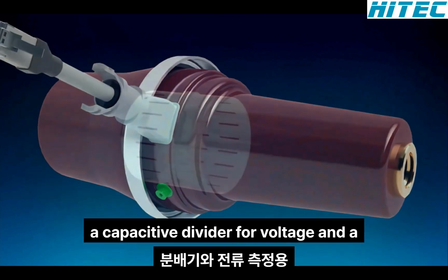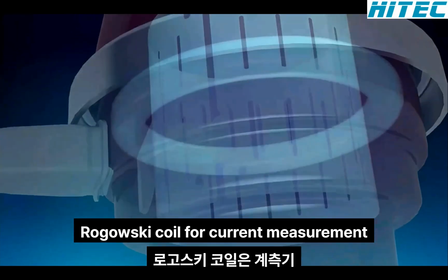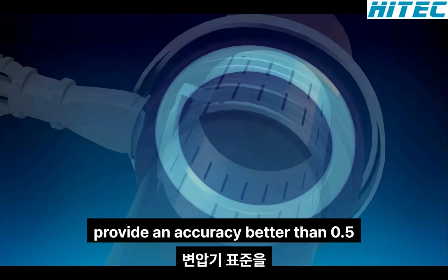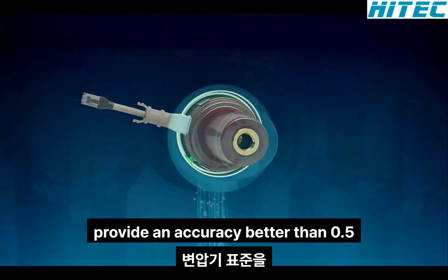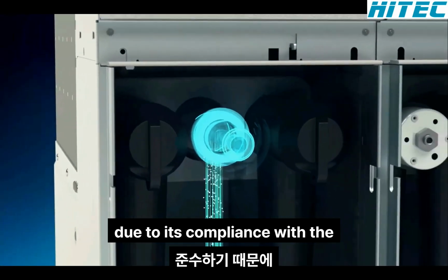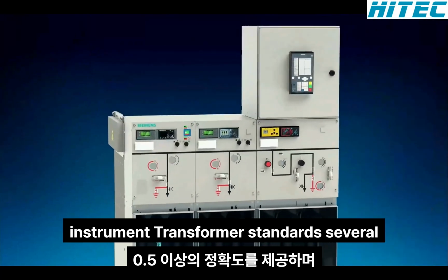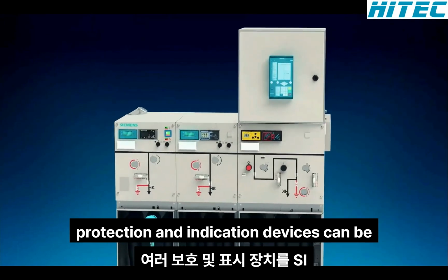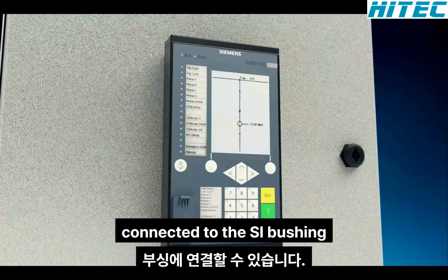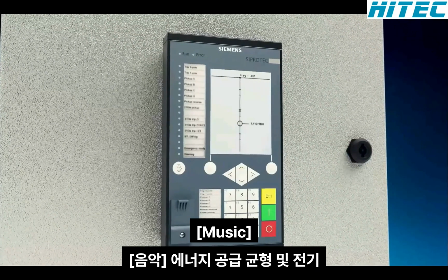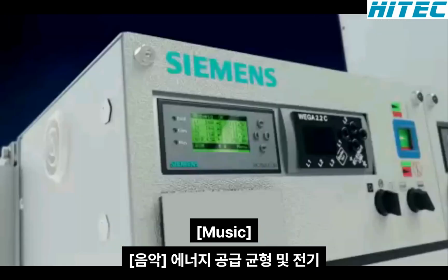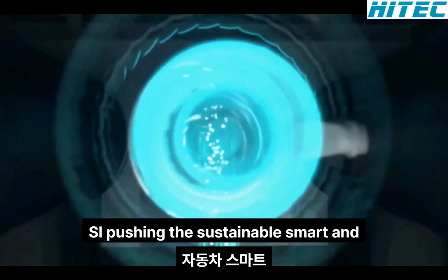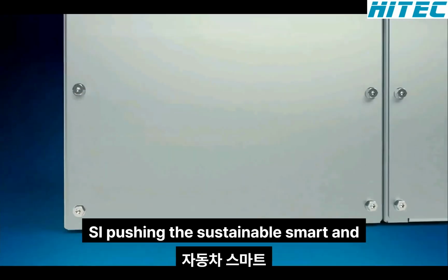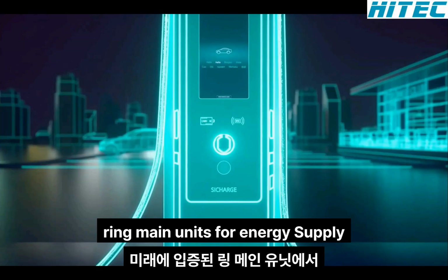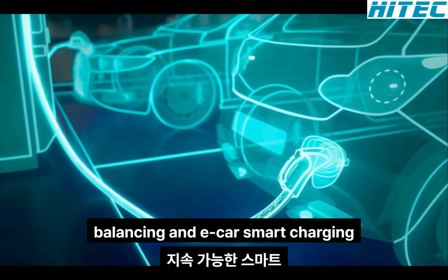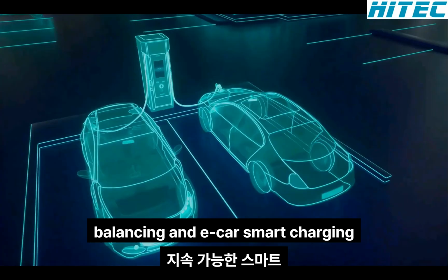A capacitive divider for voltage and a Rogowski coil for current measurement provide an accuracy better than 0.5. Due to its compliance with the instrument transformer standards, several protection and indication devices can be connected to the SI bushing. SI bushing, the sustainable, smart, and intelligent solution in future-proven ring main units for energy supply balancing and e-car smart charging integration.